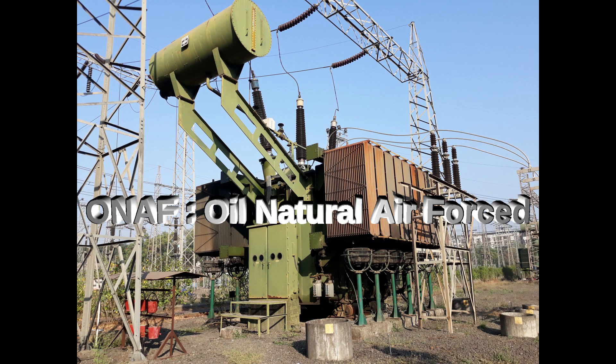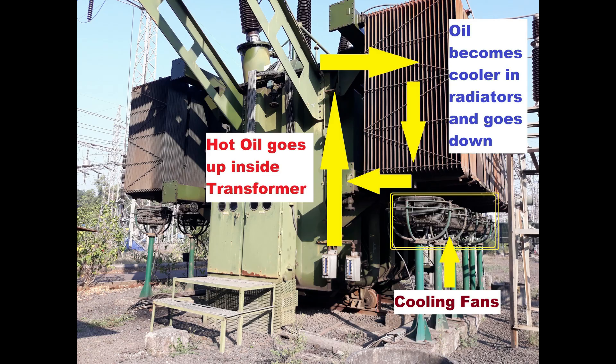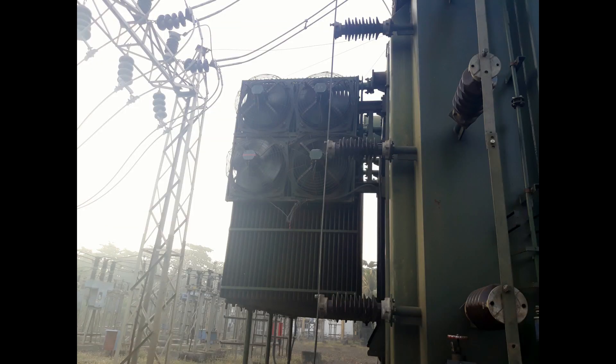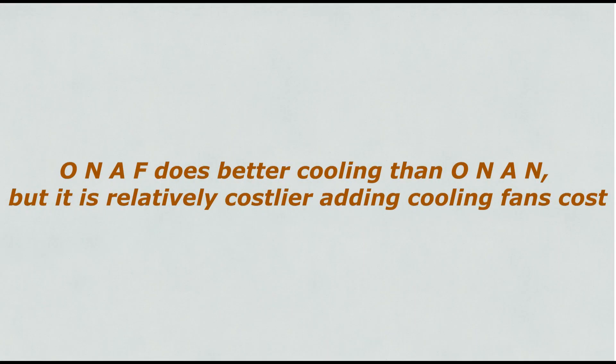ONAF — meaning oil natural air forced. This cooling system works the same as ONAN, except in this case airflow is forced with cooling fans. Cooling fans are normally fitted at the bottom of radiators facing upward. The reason is that air at the bottom is relatively cooler, so fans at the bottom forcing air from bottom to top will give more effective cooling. Cooling fans are fitted sideways also, suitable to the design. ONAF does better cooling than ONAN, but it is relatively costlier due to the added cooling fans cost.